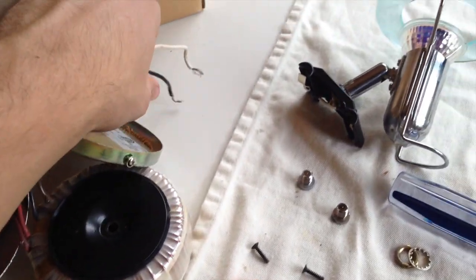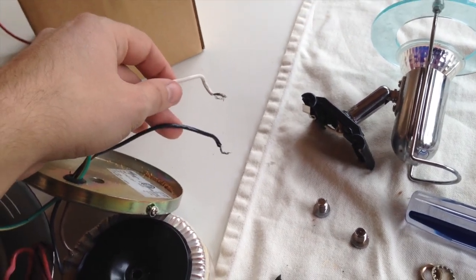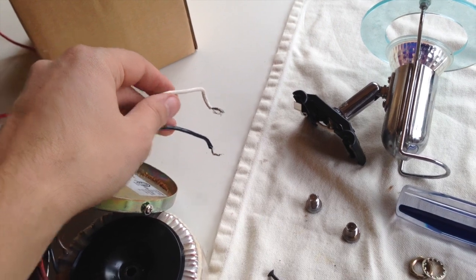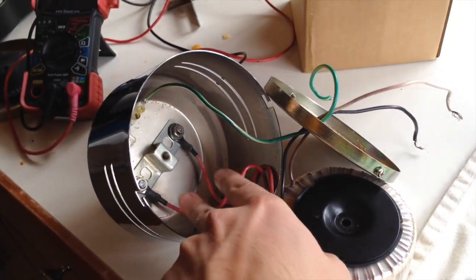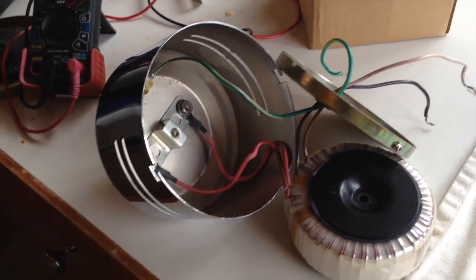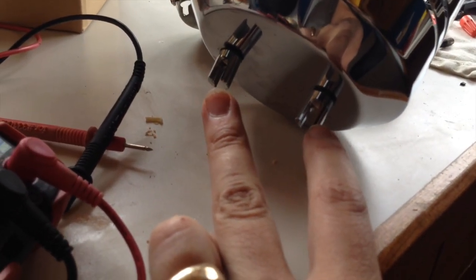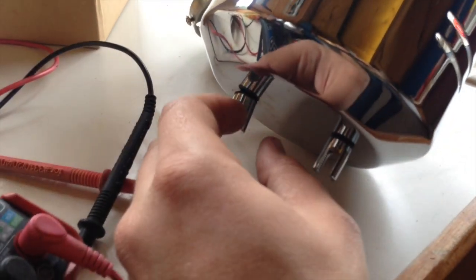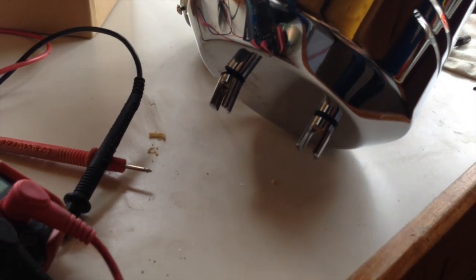On the one that's been in service, we've got a good reading here, 0 ohms, and a good reading here. However, what I think might be the problem is that when I take a reading at these posts, I get 5 kiloohms. Not quite open, but when it stopped functioning, for a while it would intermittently function, and if I jiggled this, it would work. So I'm guessing there's a bad connection somehow in this enclosure winding.